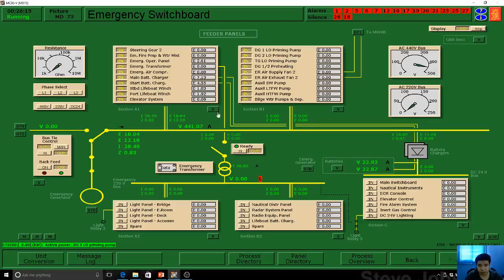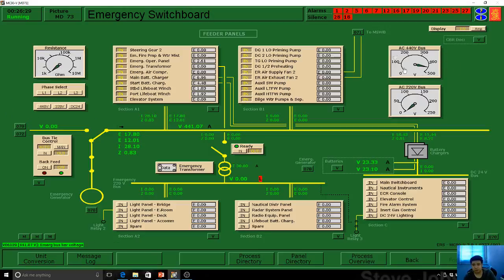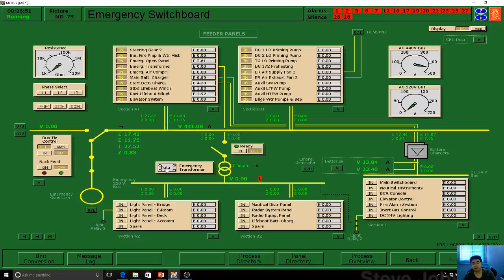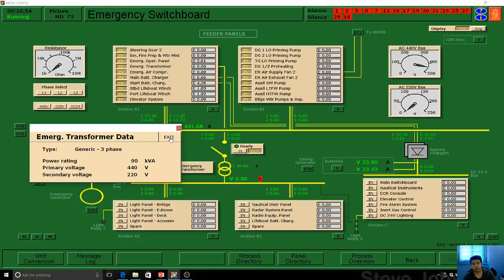Once you've switched on all feeder panels, what are the parts of this emergency switchboard? You have a resistance for earth fault testing. You have an AC voltage of 440V. There is an emergency transformer — three-phase, 90 kilovolt-ampere — with primary voltage of 440V being converted to 220V. Every time you see data, you just click on it and you can check what's inside.